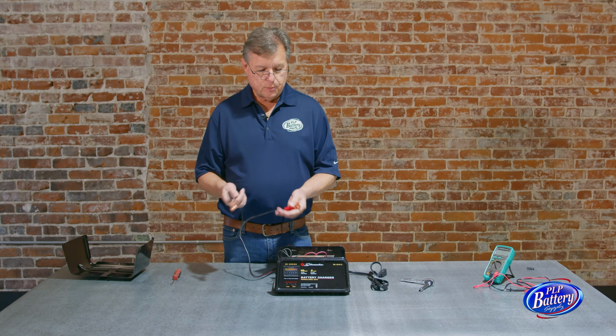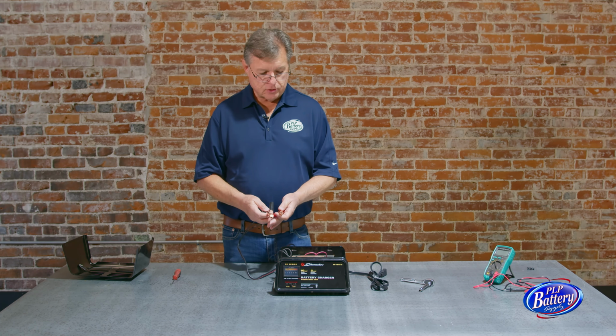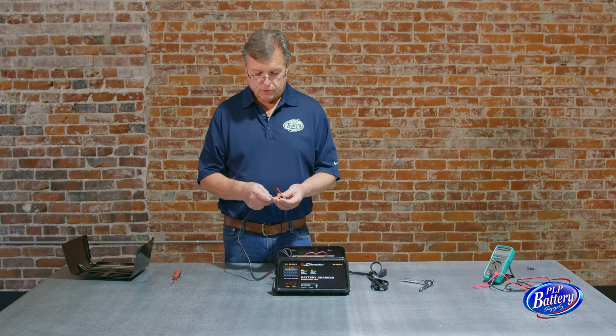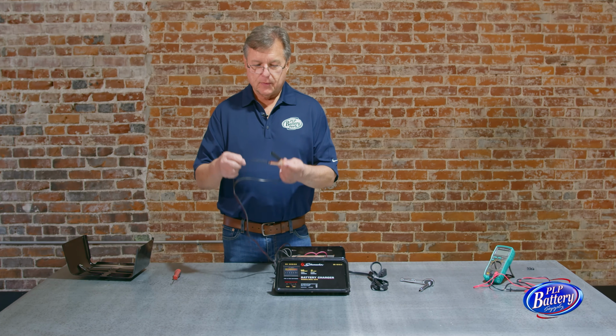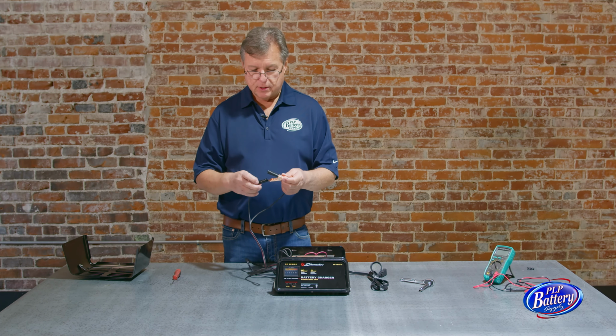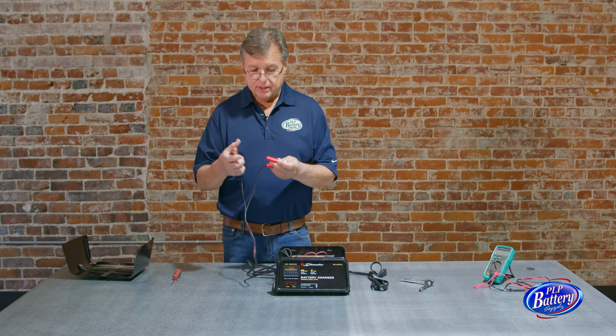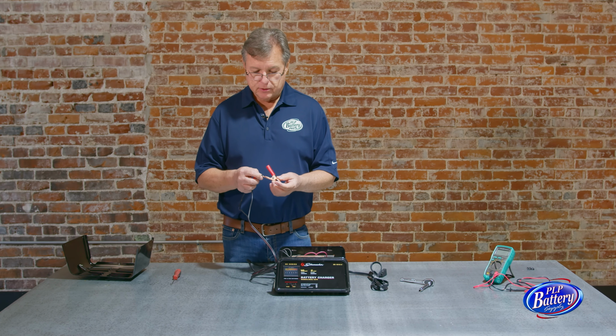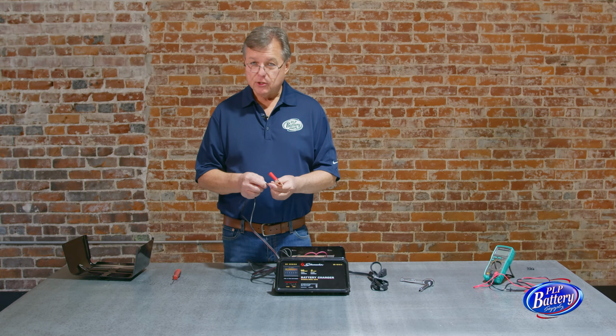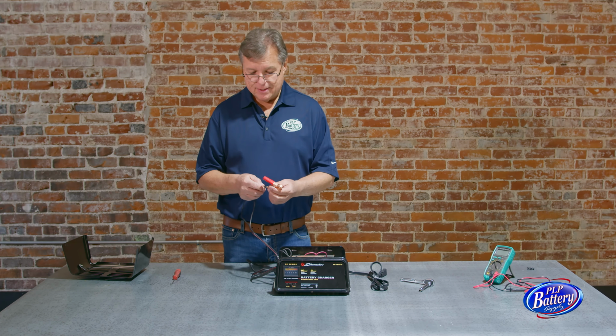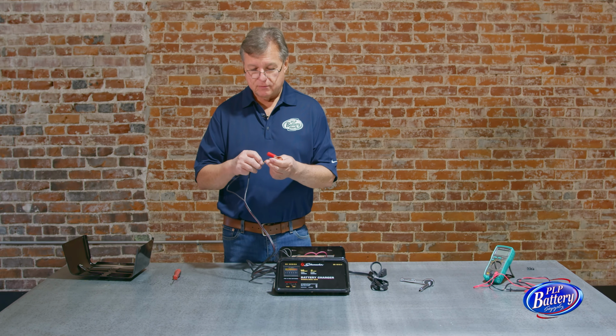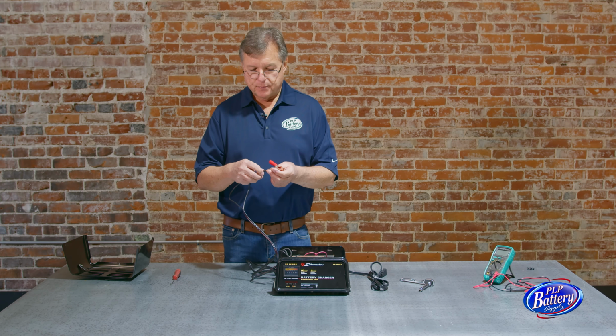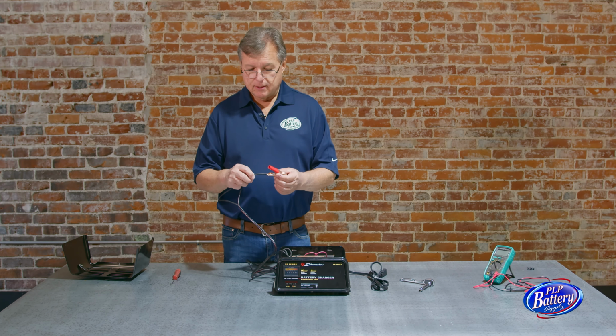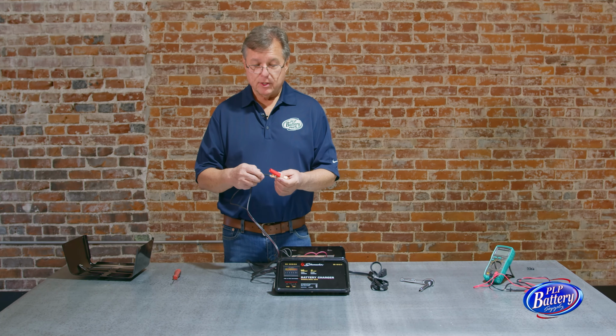But when you pull this thing and put it on the bench, before you ever pull the cover off, take a look at this part of the clamp on both sets, on the positive and the negative, and see what it looks like. If it's loose, if it's been getting hot, if the insulation's melted away a little bit, if part of that wire is exposed, that's all related to being high resistance. And high resistance typically means loose. You just need to clip it off and replace it.